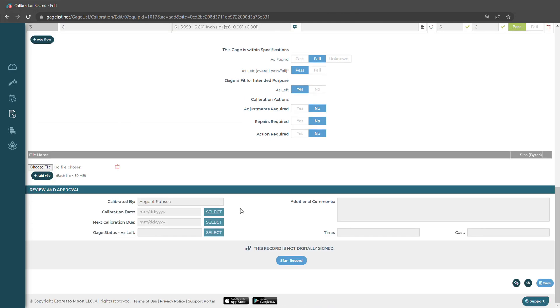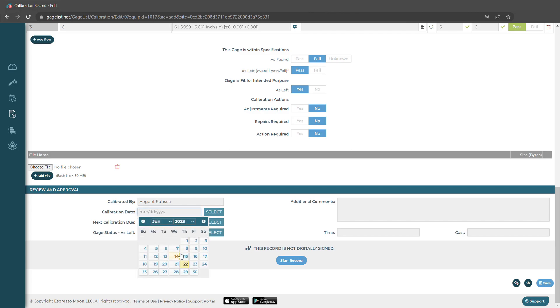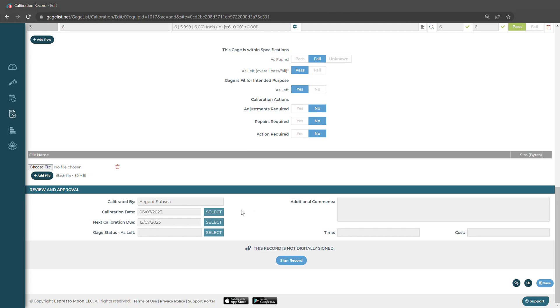If we scroll down, it'll ask us the date that we performed our calibration on. We'll go ahead and select that. And based on our scheduling information that we set up on the gauge record, it'll automatically give us our next due date based on that time frame that we set up. And we can change the status as well.